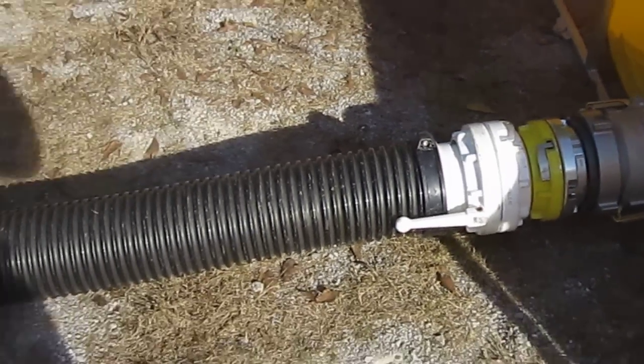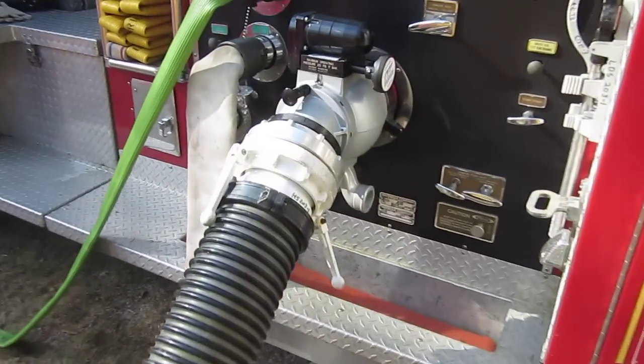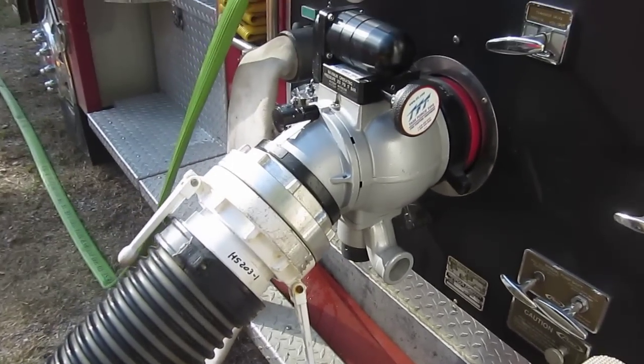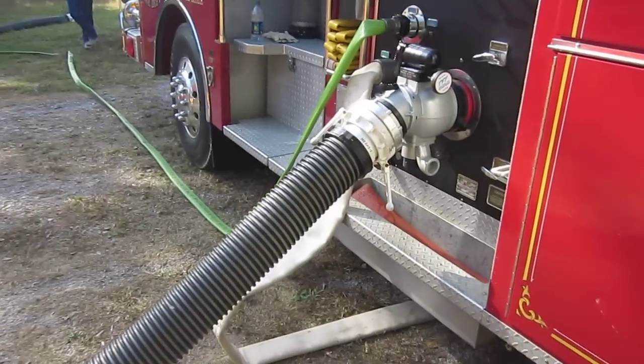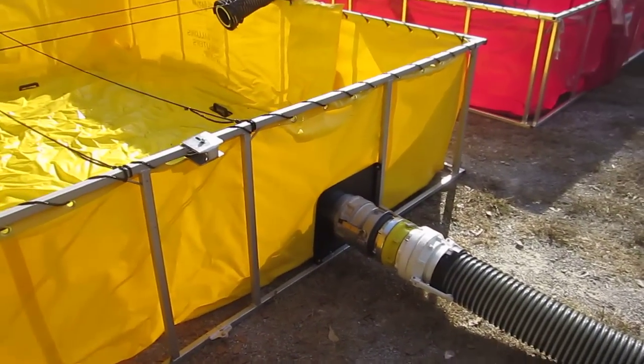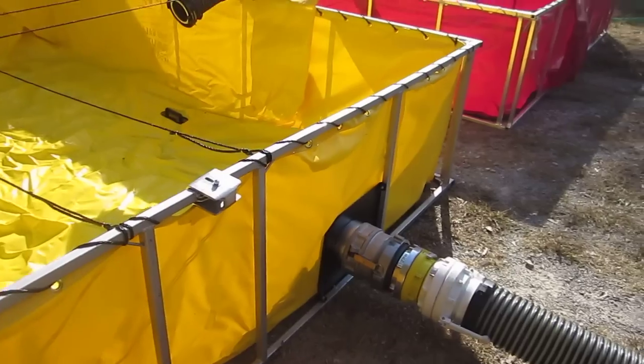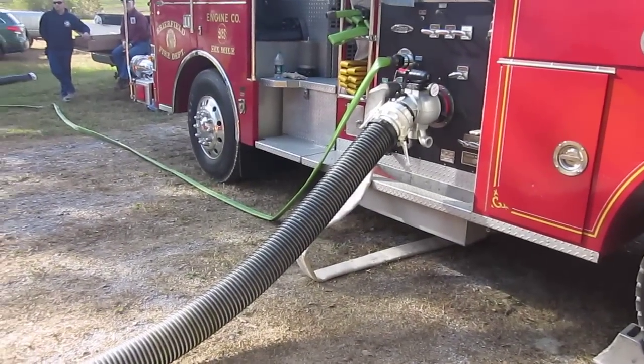The nice thing is it comes all the way back to the pumper. We have a Task Force Tips ball valve on it, should be full flow, and we're going to see what happens. We're going to try to put this different type of strainer arrangement in operation. The level of water will be the same height in the tank as back to the pump, so drafting should be pretty minimal.